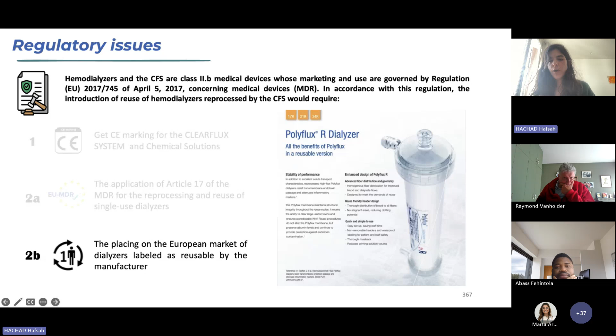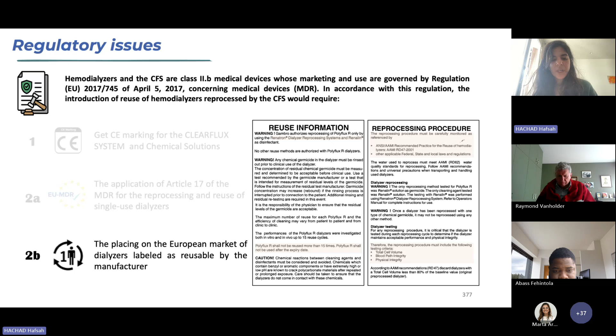And for example, here is an example of the Polyflux R Dialyzer that we presented in our study and that was tested with the ClearFlux system. And as you can see in the data sheet, the manufacturers give us the number of times it can be reused. It also gives us the recommendations that we have to apply, and exactly the steps we have to go through to have a good reconditioning.